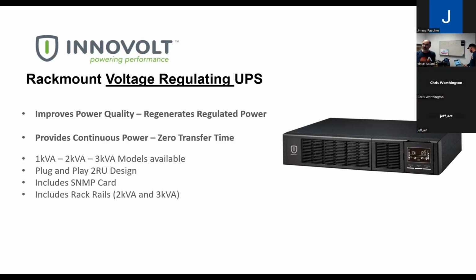The 2 kVA delivers about 17 amps, so it looks like a 20 amp circuit. Your 20 amp circuit, you don't want to load down to the full 20 amps, but it can supply whatever you're going to normally pull off of the 20 amp circuit. It does have a 20 amp plug, so one of the blades is going to be turned sideways. Make sure you have 20 amp service before you order that 2 kVA unit.